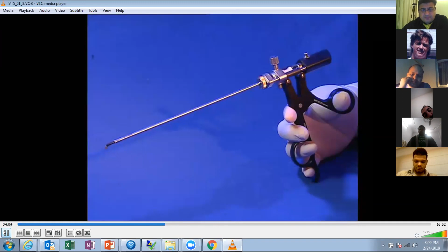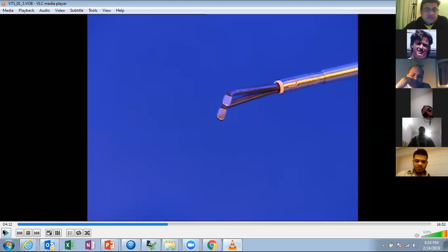Thanks to the tubular shaft design, the take-apart bipolar forceps can reach and coagulate. Now, the important technical part of this bleeding management issue: with a bipolar, maybe you are coagulating the branch of the sphenopalatine artery or the Mackenzie's artery, persistent trigeminal artery, doesn't matter. When you hold the vessel here to coagulate, you see this shaft, every time he presses the handle, this shaft is actually moving. So the vessel which is held here is not moved like this. It is not retracted. It is being held there. The shaft moves and the closure of the instrument comes so that the current can be passed and you have a hemostatic effect on vessels situated deep in the tissues. So it is just closing here. The shaft is moving. So that's the modification.